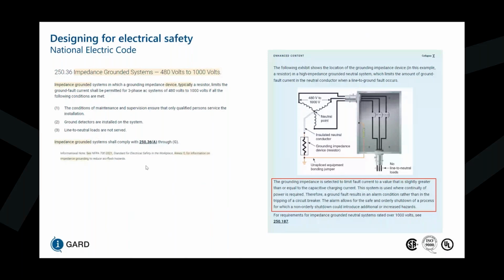The system is used where continuity of power is required. Therefore, a ground fault results in an alarm condition rather than in a tripping of a circuit breaker, and the alarm allows for safe and orderly shutdowns of a process for which a non-orderly shutdown could introduce additional or increased hazards.